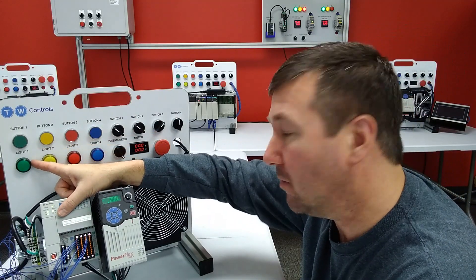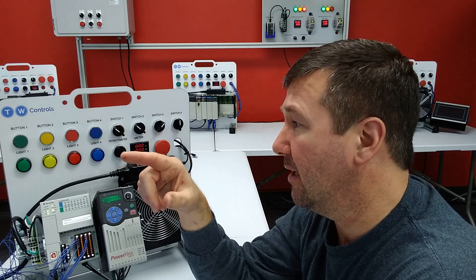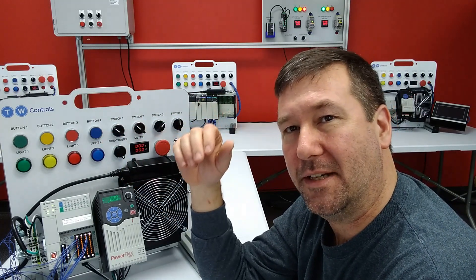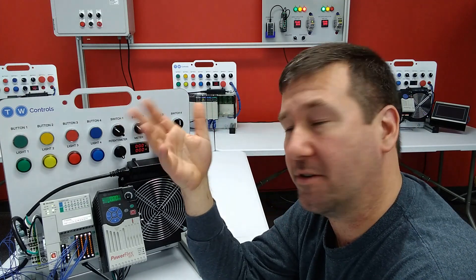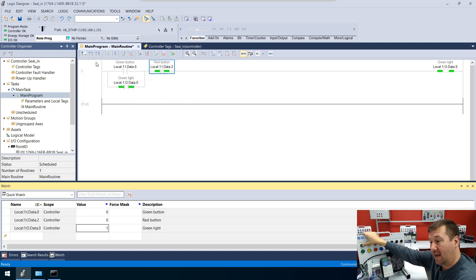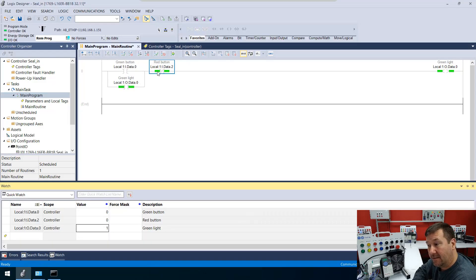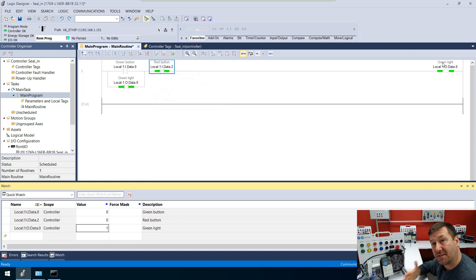Now I let off the green button. This instruction goes and looks for a one at input zero — do I have one? No. So it is false. It goes to the next branch. This instruction looks for a one at output zero — do I have one? Yes, because on the previous scan this wrote a one to it. Some of you are asking why the light is not on — well, in program mode, all the outputs go to the state they're configured for in program mode, which by default is zero. But this instruction is true. So now it goes to the examine-off and looks for a zero at input two — do I have one? Yes, so it's true. This upper branch is now false, but this lower one is true, so we have a continuous path of trues from left to right, and that is going to write a one to output zero — keeping that output sealed in. When the red button is pressed and becomes a one, this examine-off instruction is false, which makes the output false, and that's what turns it back off.